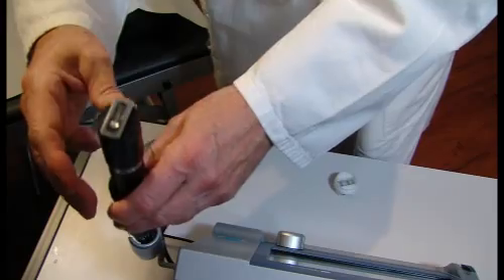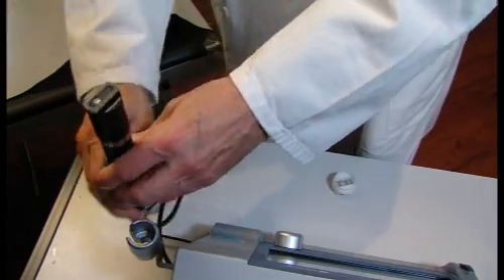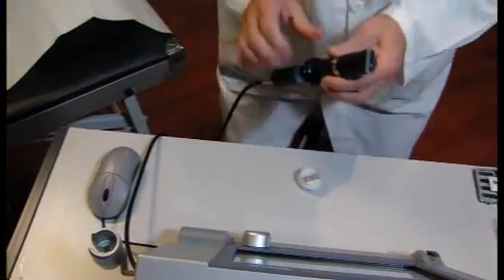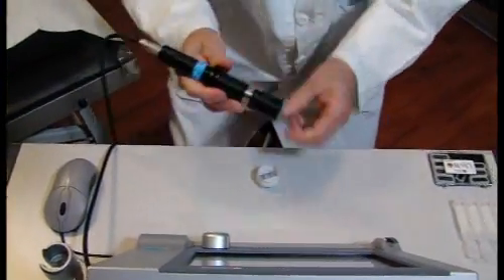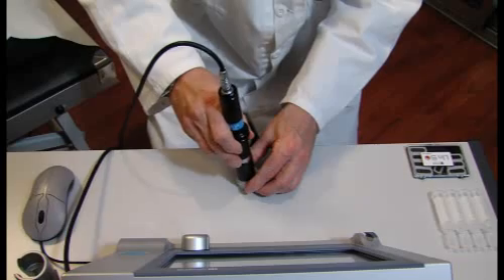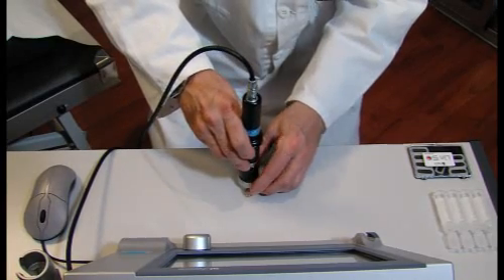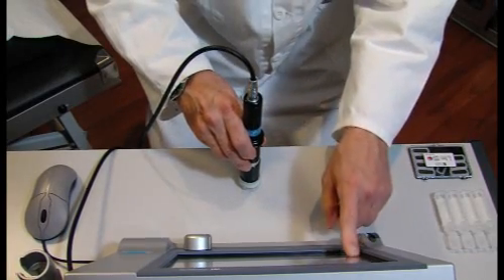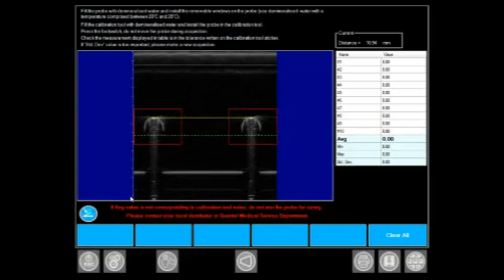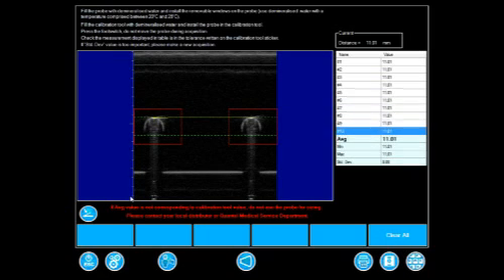The doctor picks up the probe and places it on the checking tool previously filled with water, then presses this button to start the automatic calibration. The checking is now complete.